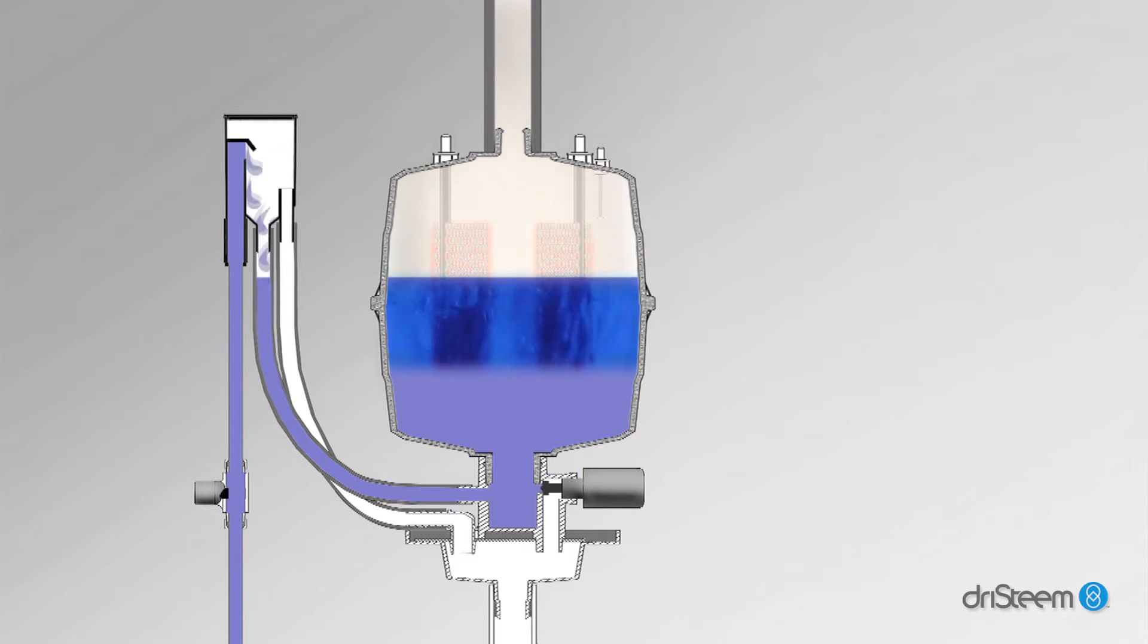The fill valve remains open until the water level rises to a maximum level set by the controller, then the fill valve closes and the water continues to boil into steam.